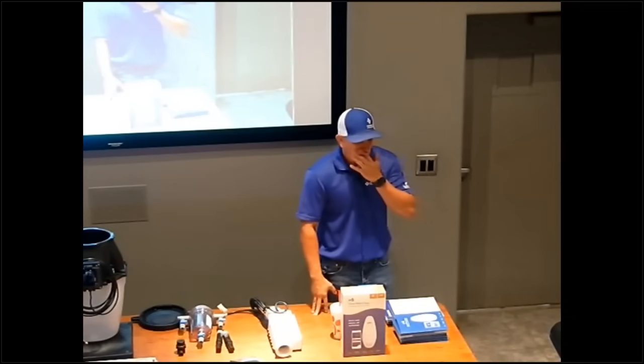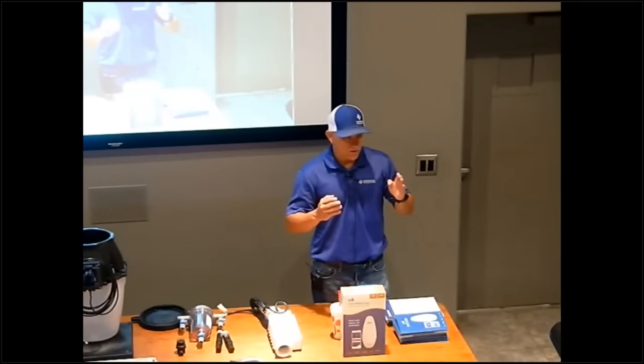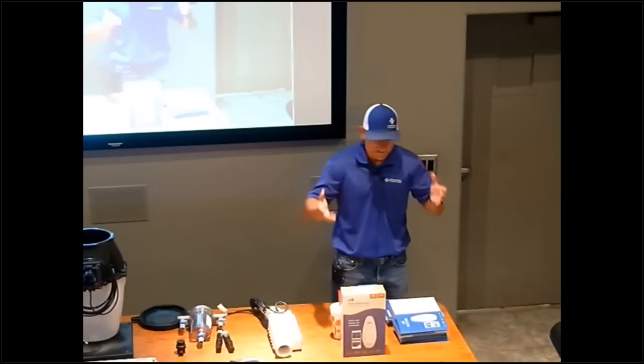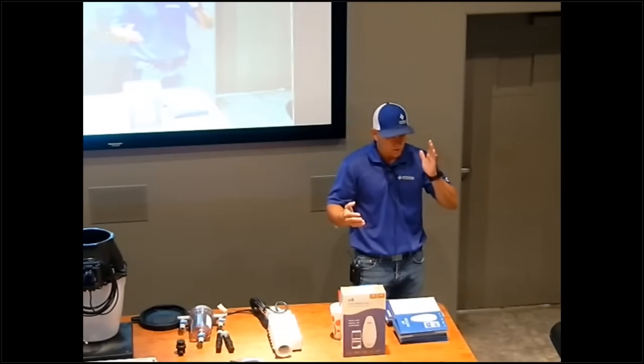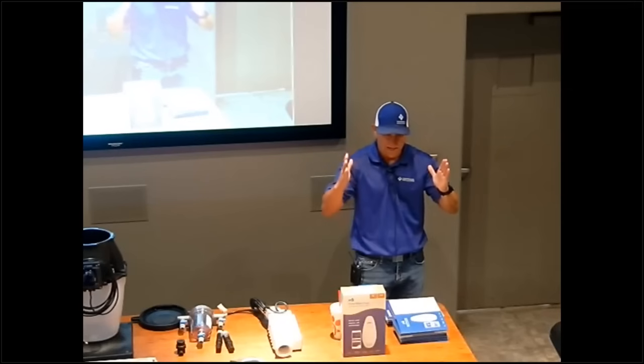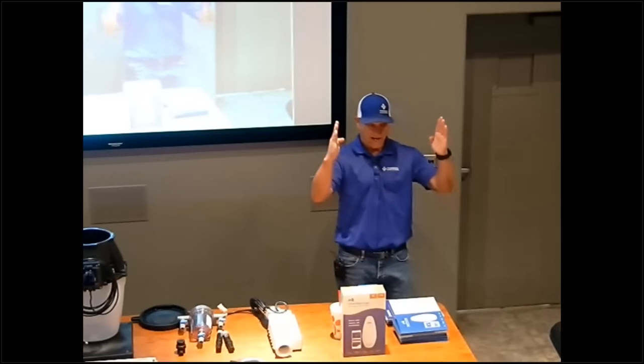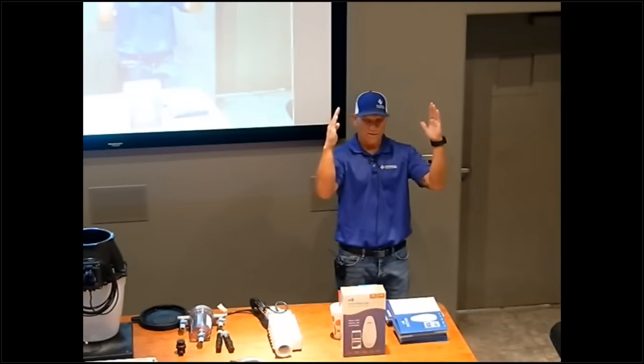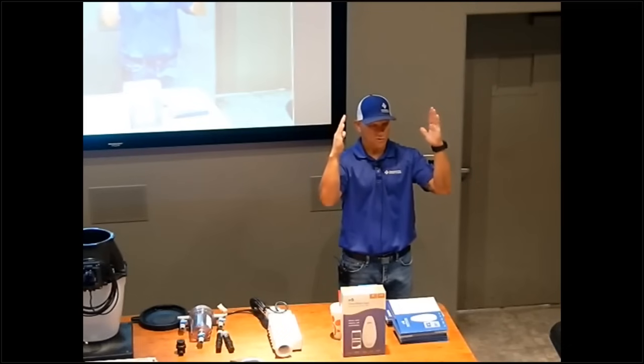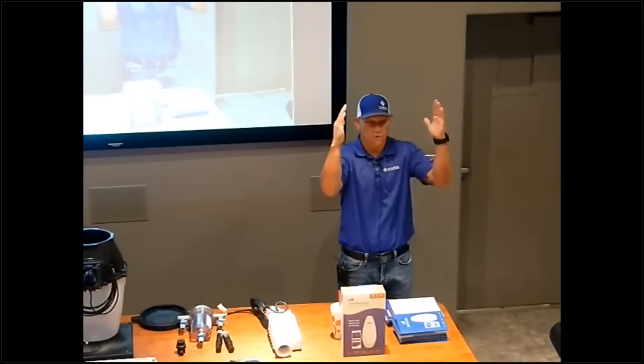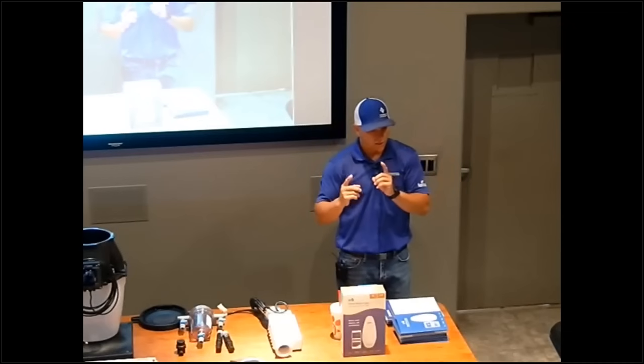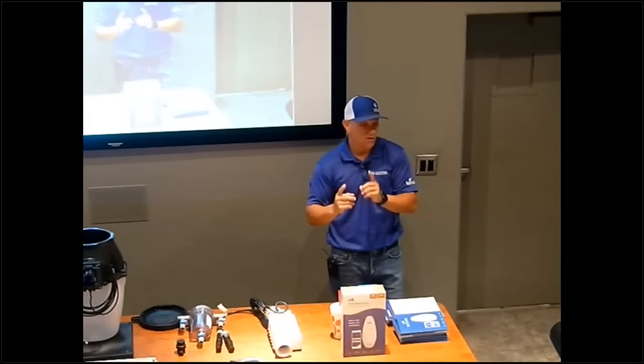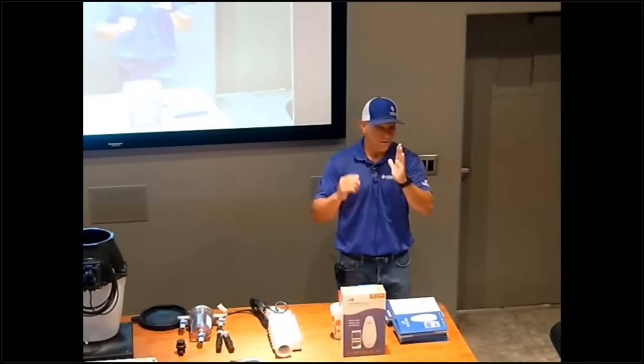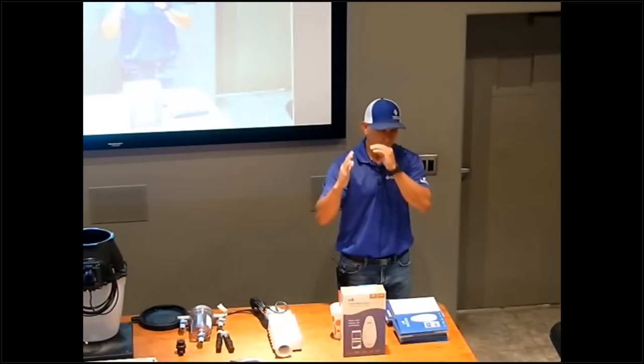What you want to do is, I always say 12 to 8 just because it's easy. Set your low speed from 12 a.m. to 8 a.m. — now you've got an 8-hour window of low speed. That doesn't mean the pump runs low speed for all 8 hours, you've just set the window. Then take your high speed schedule and set it for, say, 4 a.m. to 8 a.m.